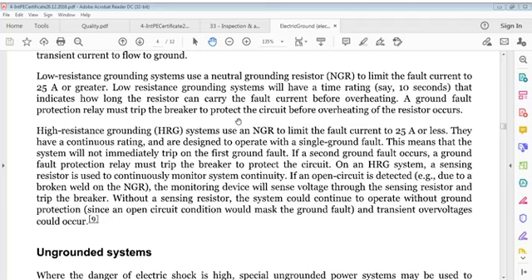High resistance grounding systems use an NGR, again a neutral grounding resistor, to limit fault current to 25 amperes or less. They have a continuous rating and are designed to operate with a single ground fault. This means the system shall not immediately trip on the first ground fault. If a second ground fault occurs, a ground fault protection relay must trip the breaker to protect the circuit.